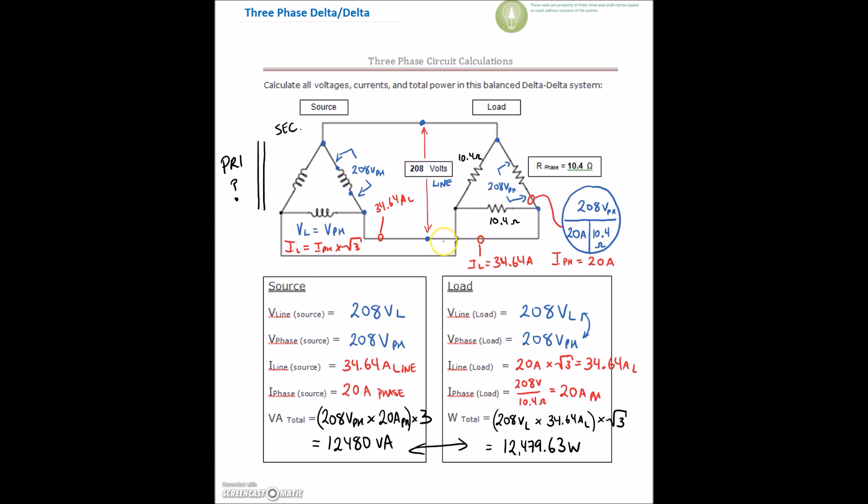So we take 20 amps times root 3, and it gives us 34.64. That current is flowing on this line right here. So we have 34.64 on the line. And on the inside, this winding right here and this winding are both providing 20 amps, just 120 degrees at a phase, to provide us with that 34.64 amps on the line.